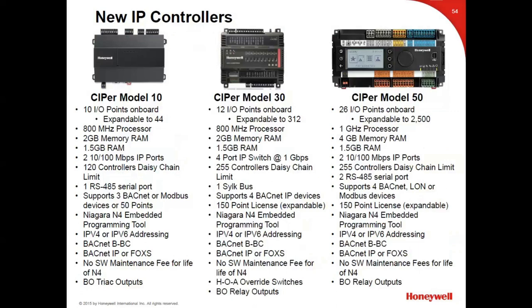Controller comparison: the CIPer 10 and CIPer 30 have an 800 MHz processor and 2 GB RAM, while the CIPer 50 has a 1 GHz processor and 4 GB RAM — same as a JACE. The CIPer 50 is effectively a JACE; the CIPer 10 and 30 are small JACEs. The CIPer 30 includes a Sylk bus, so you can use Sylk sensors on it — not available on the 10 or 50. The CIPer 30 is expandable up to 312 points with up to 15 IO modules. Importantly, there is no software maintenance fee for the life of Niagara 4 for these controllers — different from a JACE.